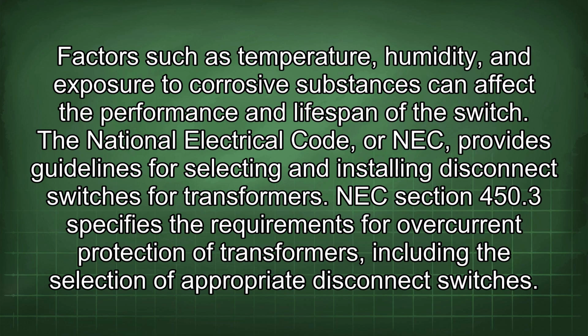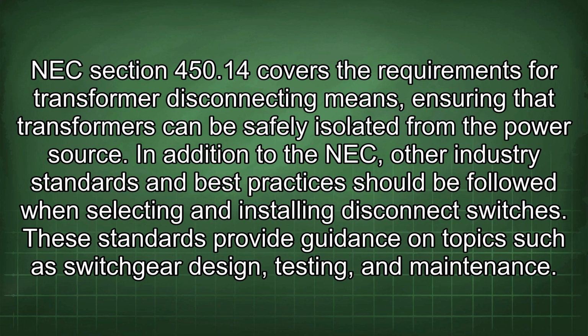The National Electrical Code, or NEC, provides guidelines for selecting and installing disconnect switches for transformers. NEC Section 450.3 specifies the requirements for overcurrent protection of transformers, including the selection of appropriate disconnect switches. NEC Section 450.14 covers the requirements for transformer disconnecting means, ensuring that transformers can be safely isolated from the power source. In addition to the NEC, other industry standards and best practices should be followed when selecting and installing disconnect switches. These standards provide guidance on topics such as switchgear design, testing, and maintenance.